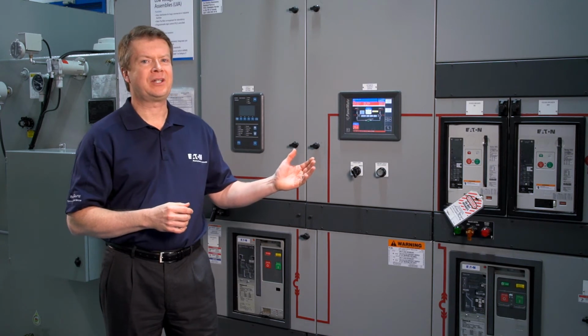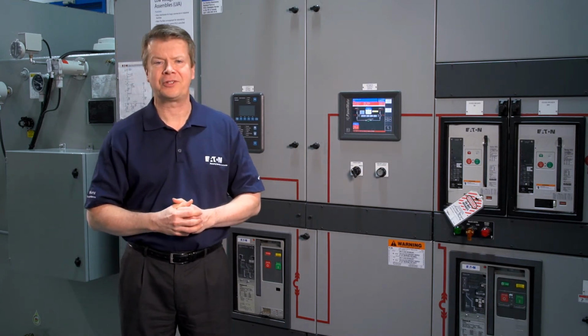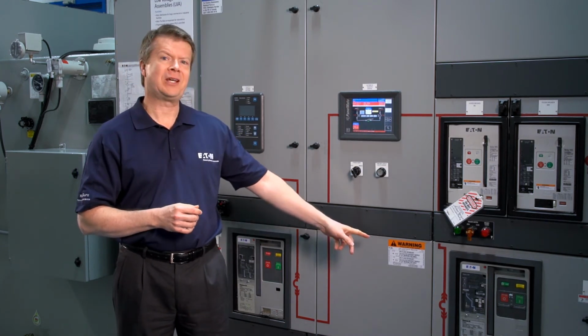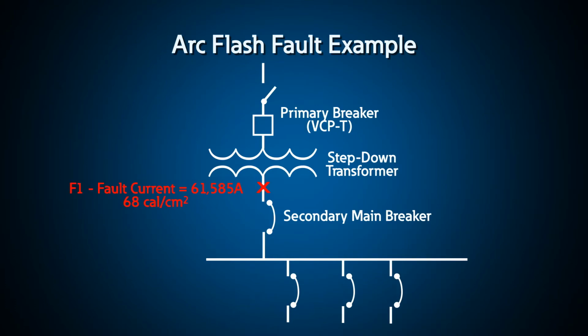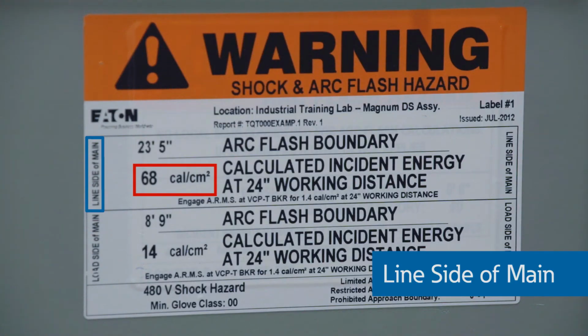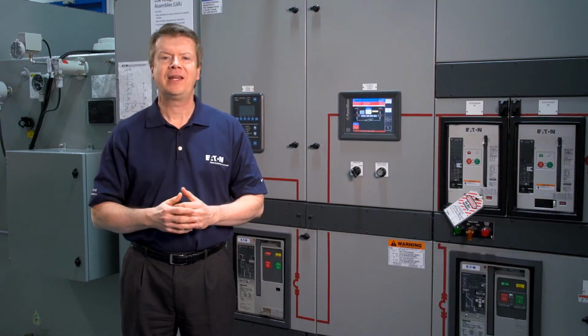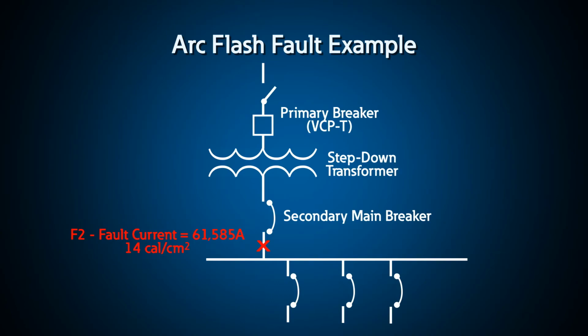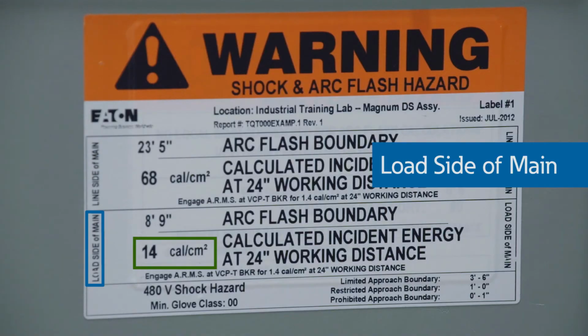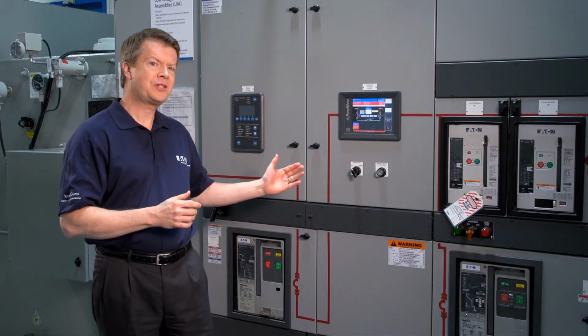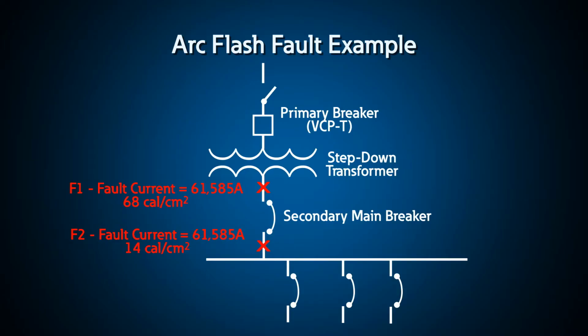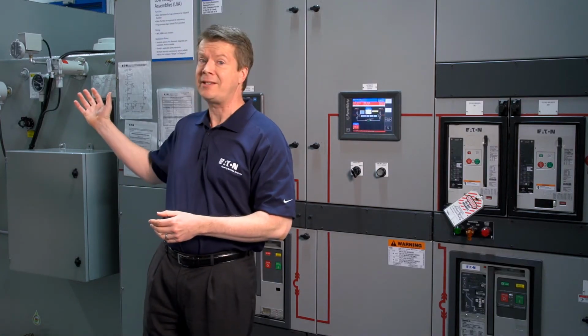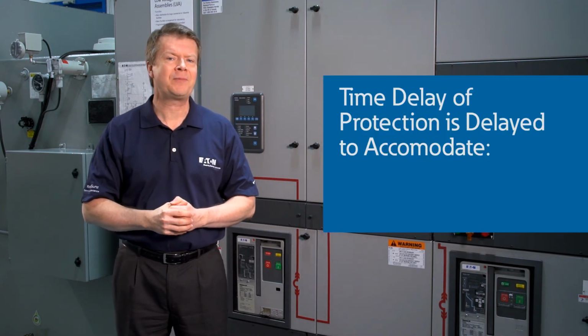This low voltage assembly illustrates a very common yet very dangerous situation. The arc flash label indicates that the arc flash energy on the primary side of this breaker is 68 calories, well above the maximum allowed when wearing a 40-calorie suit. Yet on the secondary side of the breaker, it is only 14 calories. For a fault on the secondary, this breaker can trip quickly. For a fault just on the other side of this breaker, even though the fault current is the same, the energy is much higher because the clearing time of the nearest upstream device is intentionally delayed to compensate for transformer inrush and coordination.